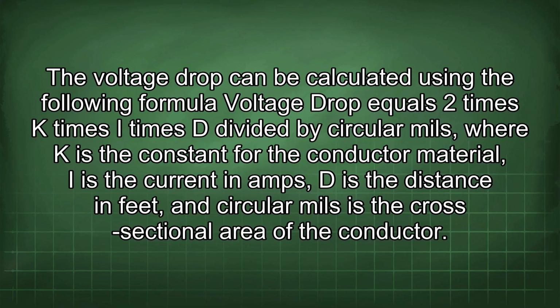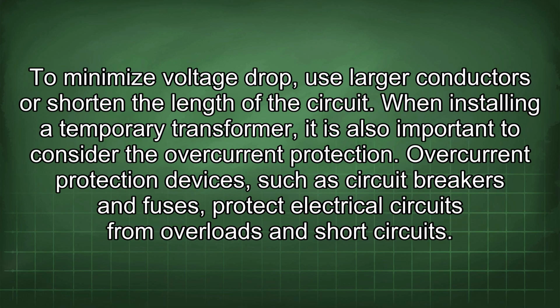times I times D divided by circular mils, where K is the constant for the conductor material, I is the current in amps, D is the distance in feet, and circular mils is the cross-sectional area of the conductor. To minimize voltage drop, use larger conductors or shorten the length of the circuit. When installing a temporary transformer, it is also important to consider the overcurrent protection.